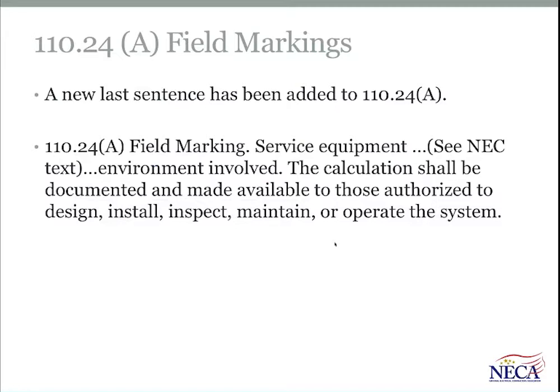110.24 is the requirement to mark service equipment with the maximum available fault current, and we all know that that requirement is in place in the NEC too, and it's related to equipment rating purposes, to make sure that equipment is not used beyond its capability or its limitations relative to available fault current. A new last sentence was added in 110.24(A), and it deals with calculations that are made to determine whether or not the equipment maintains a suitable short circuit current rating for its use.